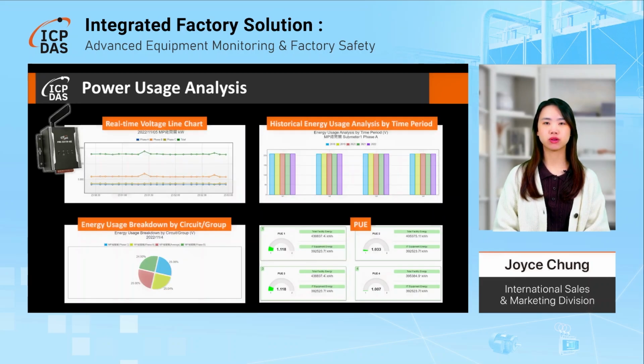The PMC module offers a variety of real-time and historical power analysis charts. In the top left, there is a real-time voltage line chart. In the top right, historical power consumption is analyzed by comparing the same season across different years to observe changes. The bottom left shows power consumption proportions, allowing multiple meters to be grouped and their usage ratios displayed. The bottom right displays PUE, or a Power Usage Effectiveness chart.